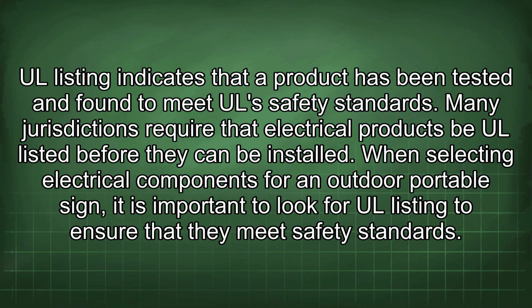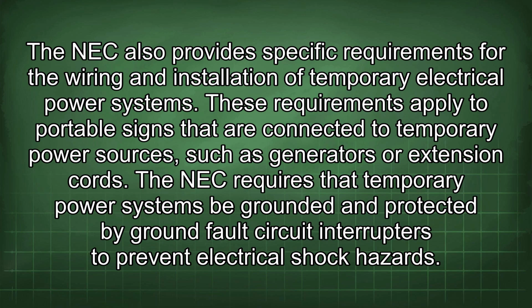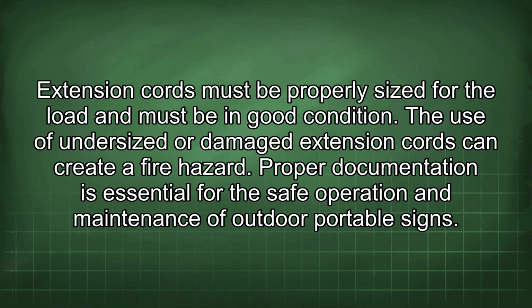The NEC also provides specific requirements for the wiring and installation of temporary electrical power systems. These requirements apply to portable signs that are connected to temporary power sources, such as generators or extension cords. The NEC requires that temporary power systems be grounded and protected by ground fault circuit interrupters to prevent electrical shock hazards. Extension cords must be properly sized for the load and must be in good condition. The use of undersized or damaged extension cords can create a fire hazard.